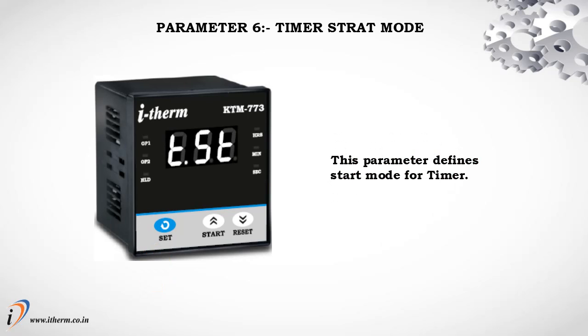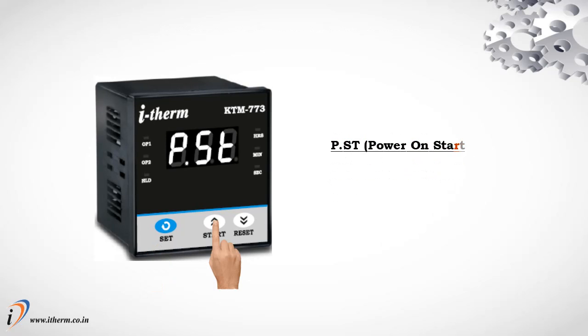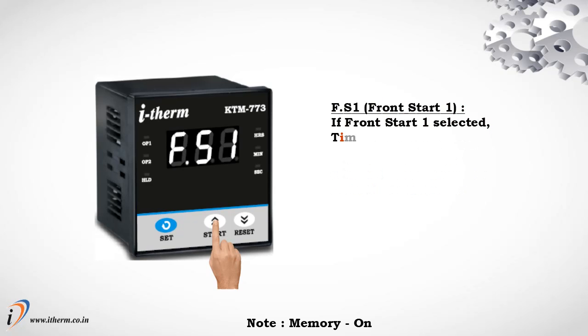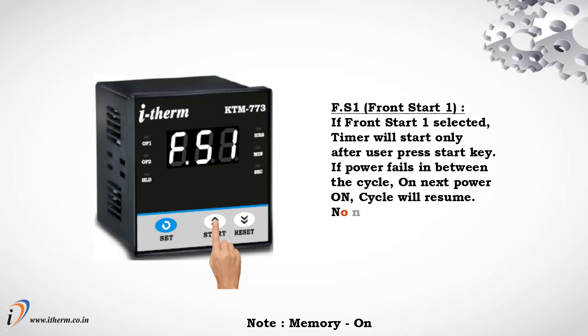Parameter 6: Timer Start Mode. This parameter defines the start mode for the timer. Power On Start: if selected, the timer will count from power on. Front Start 1: if selected, timer will start only after the user presses the start key. If power fails during the cycle, on next power on the cycle will resume — no need to apply the start command again.